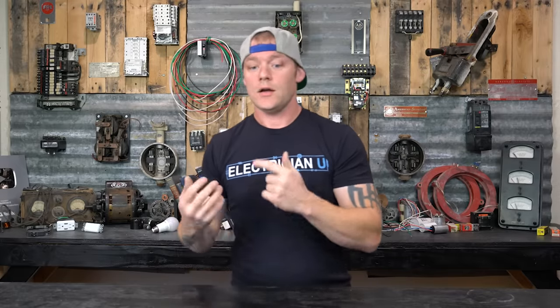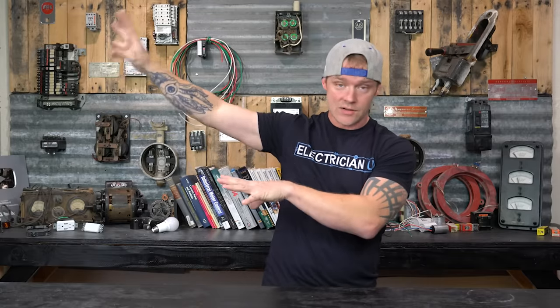To make things even more confusing, terminology is frequently interchanged. You'll see surge protection devices in store packaging that say 'surge arrest,' even though the NEC defined surge arresting as 1,000 volts or more, installed on the utility side. There's just a lot of misinformation. If you ask the average electrician, homeowner, or builder what a surge protector does, they'll say it protects against lightning — but if lightning directly hits your home, it is very unlikely a surge protector will protect it. That's not what it's designed for — it's for surges, not direct strikes.